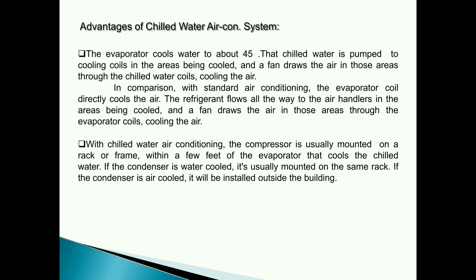The evaporator cools water to about 45 degrees. That chilled water is pumped to cooling coils in the areas being cooled, and a fan draws the air in those areas through the chilled water coils, cooling the air. In comparison, with standard air conditioning, the evaporator coil directly cools the air — the refrigerant flows all the way to the air handlers in the areas being cooled, and a fan draws the air through the evaporator coils. With chilled water air conditioning, the compressor is usually mounted on a rack or frame within a few feet of the evaporator that cools the chilled water. If the condenser is air-cooled, it will be installed outside the building.